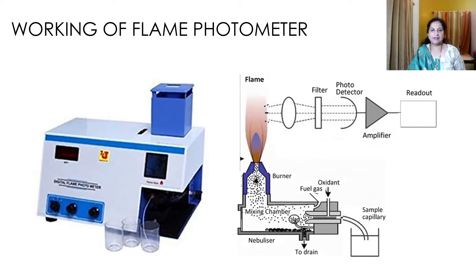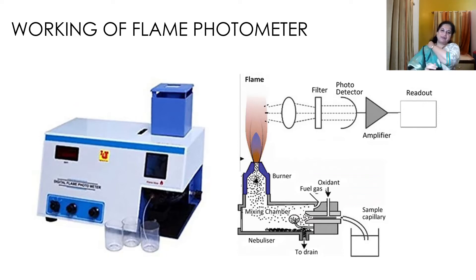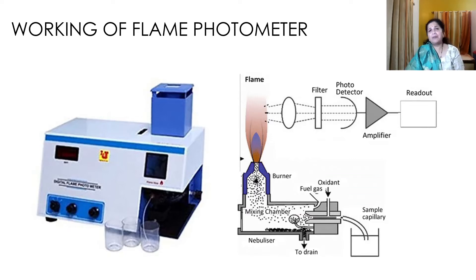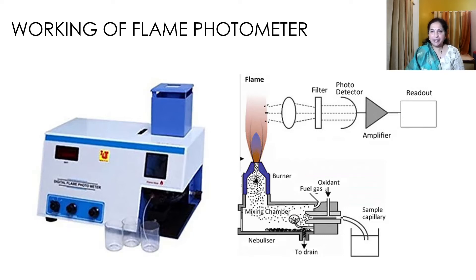On one side you can see the flame photometer instrument, and on the other side I have represented a schematic diagram of the process. Basically, the sample to be analyzed is sucked and aspirated to the burner. The sample is sprayed over the flame as fine droplets. Everything happens in the flame and the light emitted by the sample is sent to the detector by the usual optical system. On the digital display, we get a reading which we note down as emission intensity.